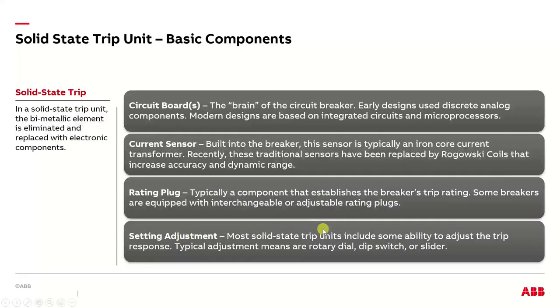Setting adjustment. Most solid state units have at least some adjustability to them. Like I said before, it could be something that just moves the instantaneous up and down, or it could be full LSI or LSI with ground fault. And the typical adjustments were a rotary dial, dip switches, which ABB uses, and slider switches. So that's how you'd make your adjustment.